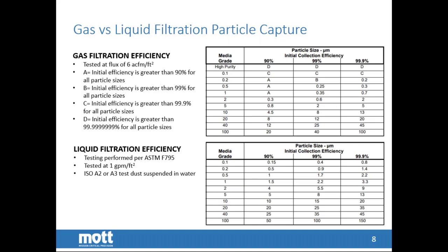With regards to filtration, there's gas filtration and liquid filtration. We refer to our porous micron size as media grade versus micron, because there is a difference in the filtration efficiency between gases and liquids. As you can see from this graph, gas filtration is at quite a bit higher efficiency than liquid filtration.